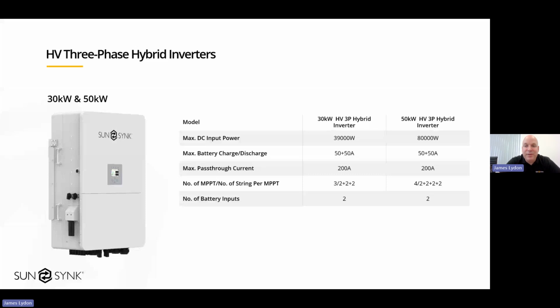And then the 30 kilowatt and the 50 kilowatt. The 30 kilowatt has a 39 kilowatt MPPT, and the 50 is bigger in terms of percentage oversize. You can connect up to 80 kilowatt into the 50 kilowatt. Paralleling the high voltage inverters, you can parallel 10 of these, so you can have 10 50 kilowatt hybrid inverters connected in parallel. As you can see on the MPPTs, the larger we go, the more MPPTs we've got. On the 50, there's 4, each with 2 strings into each. And the 30 and the 50 kilowatt both have 2 battery inputs.